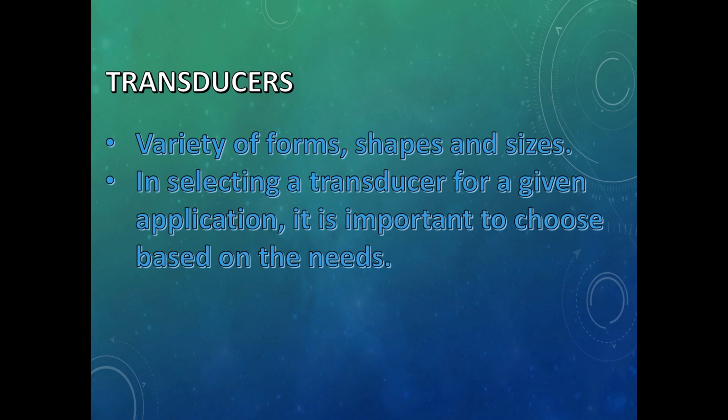Transducers are manufactured in a variety of forms, shapes, and sizes for varying applications. In selecting a transducer for a given application, it is important to choose based on the needs such as desired frequency, bandwidth, size, and in some cases focusing, which optimizes the inspection capabilities.